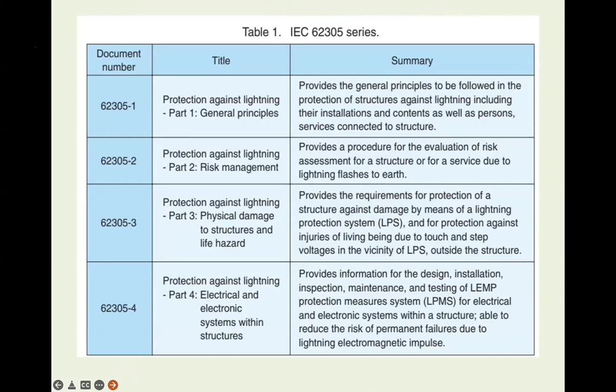You must have IS code 3043 on earthing. You must have IS 732 on electrical wiring installation. You must have IS IEC 62305 on protection against lightning, which has 4 parts. Part 1 talks about general principles, part 2 talks about risk management, part 3 talks about physical damage to structures and life hazard, and part 4 talks about electrical and electronic systems within structures.